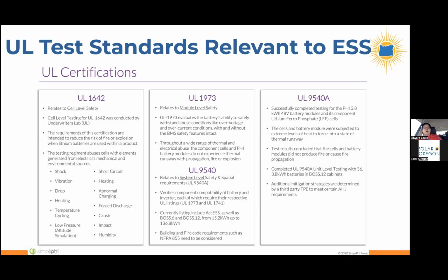And then most interesting of all is the UL 9540 series of tests. These are what's called large-scale fire testing of lithium batteries. You would get a module and set it on fire, to understand how the fire will propagate from cell to cell or from module to module. The fire testing procedure is outlined in the UL 9540A standard. And the findings from that test procedure are written out in a UL 9540 document to write out the results.